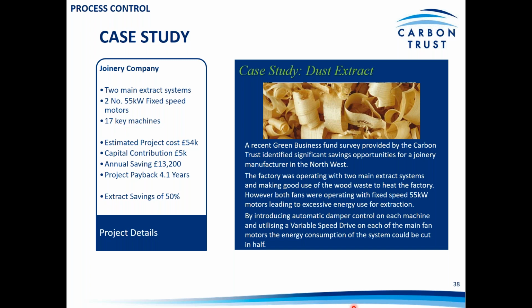The cost that was estimated was about £54,000, and we were able to offer a contribution in this case of £5,000. Annual saving 13,200 there, with a project payback of about 4.1 years. But I suppose the key thing in this one really is the level of extract savings. So you could see there that the energy use on the extract system was halved by introducing the variable speed drives and the damper control to minimize the energy use there.